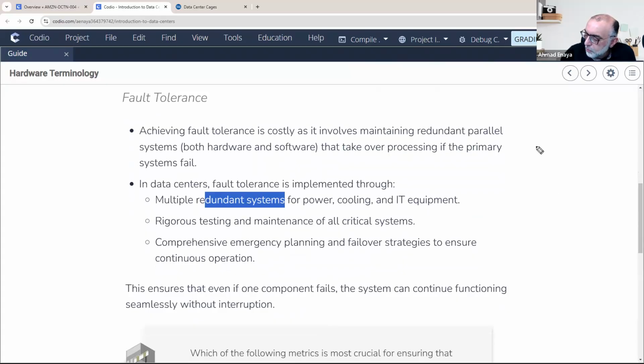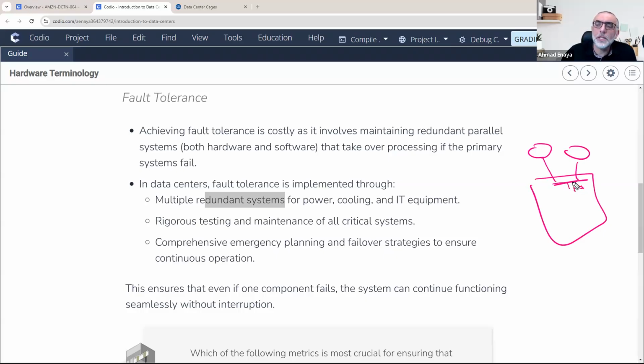Let's say you have 2 generators feeding your data center, and they are connected to your data center in a bus bar, and they have some sort of ATS. We'll talk about them. If you have redundancy, but you have never tested your redundancy, and you always rely on the primary generator, you have never tested your secondary generator, and one day this one fails, and the commercial power fails, and only at that time you discover that the connection here is faulty, and this generator is running without feeding your data center. Do you have redundancy? Yes, you do have redundancy. You have 2 generators. But guess what? You have never tested your redundancy. You have never run or enabled or tried to test this redundancy in real life. And that's why you have redundancy, but you don't have availability.